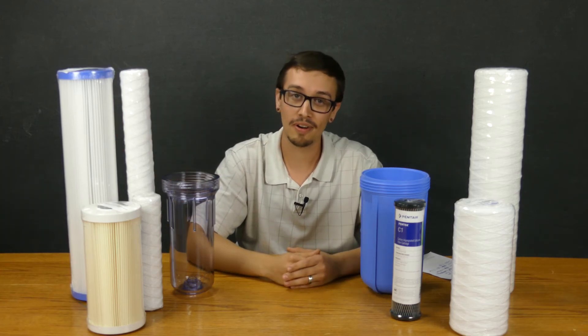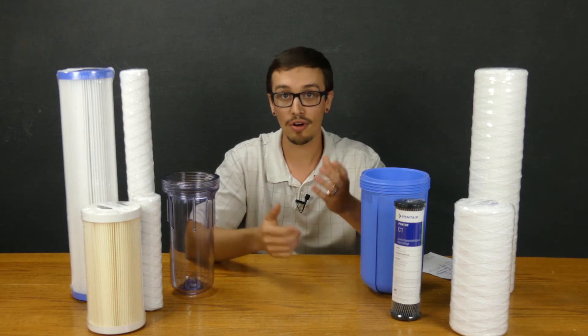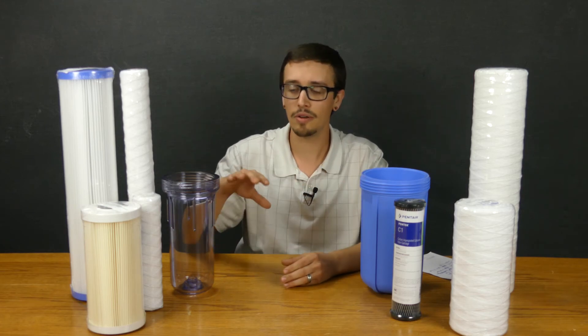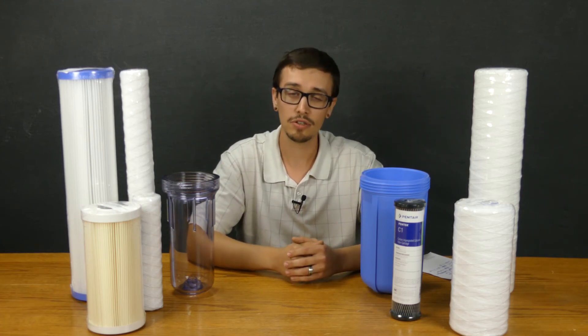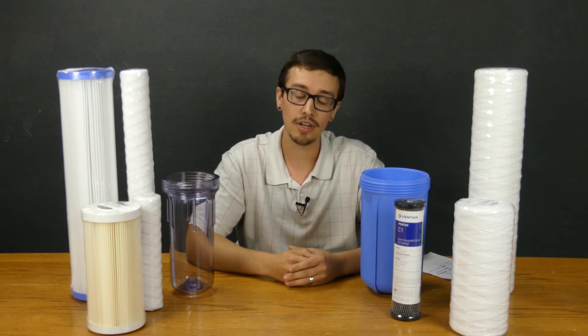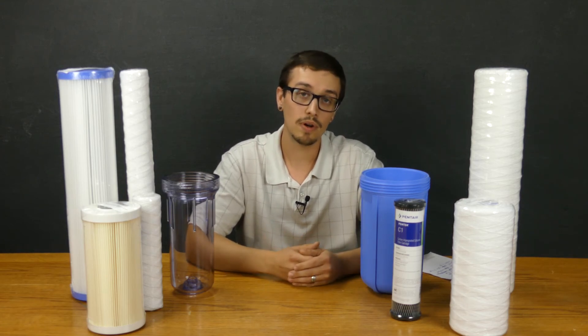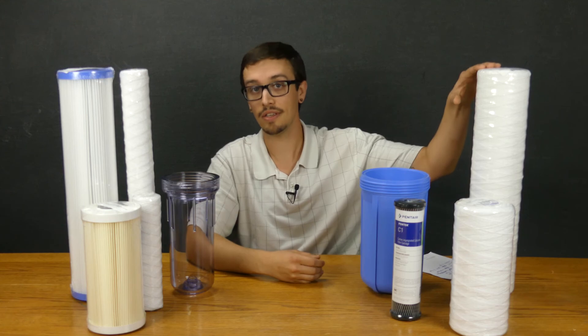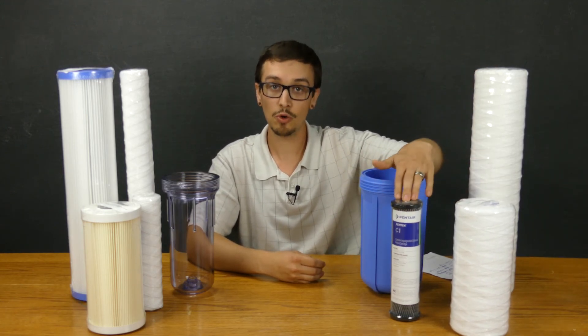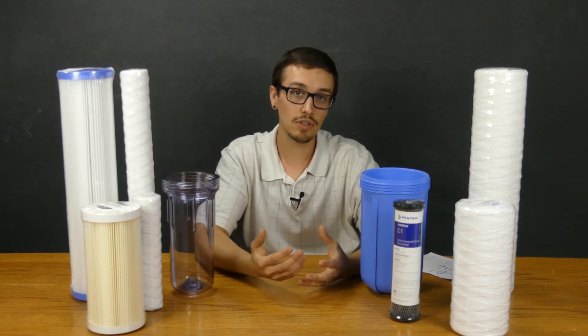That about sums up our basic overview of filters and what you can expect and why there are various sizes. The one last thing I'll leave you with is that the sizes we have here represented are essentially standard sizes. There's really only four major sizes that you're going to encounter with filters. You're going to encounter the 4.5 by 20 inch filters, which is what this size is. You're going to encounter 4.5 by 10 inch filters, which is what this size is. And then 2.5 by 10 inch and 2.5 by 20 inch. Those are essentially the only four.